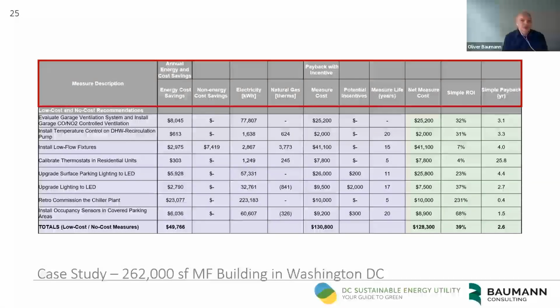So you start with the description of your measure, then your annual energy costs and savings, energy cost and non-energy cost savings - I'll get to that in a moment. You have your electricity in kilowatt hours, your natural gas in therms, and if you have steam or other energy sources those would show up in this table too. Then you indicate the cost of the measure - you estimate the cost for material, labor, permits, and contingencies. You also identify and list potential incentives.